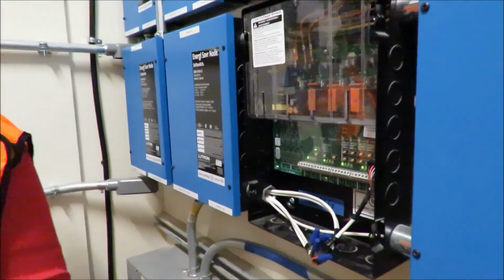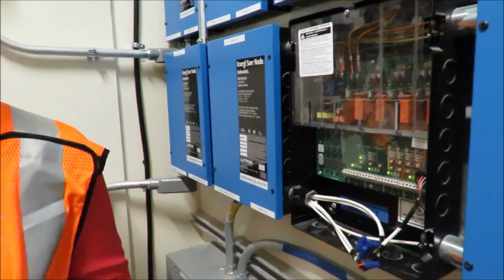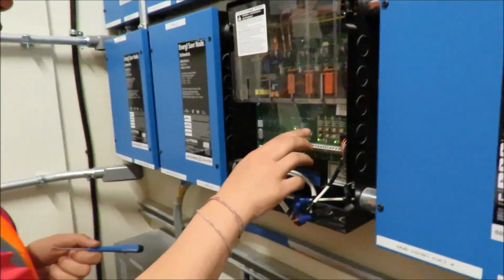It protects you from any voltage. All of your high voltages are up here, down here is just low voltage, 24 volts DC. But zone 1, you can see none of these LEDs are lit right now because it's bright outside. Okay. So these occupancy sensors work together. If someone's walking in from this way, it'll trigger all of the lights to come on. Or if there's occupancy sensors at that end and in the middle, and somebody walks in from that door, it triggers all of these lights to come on. And it's the same on every kit.